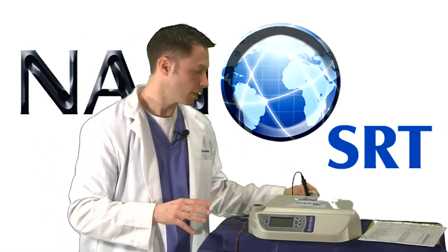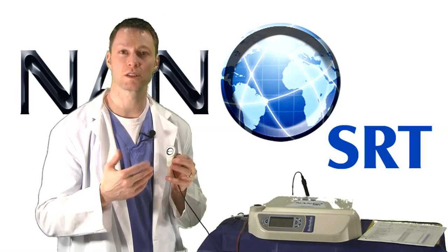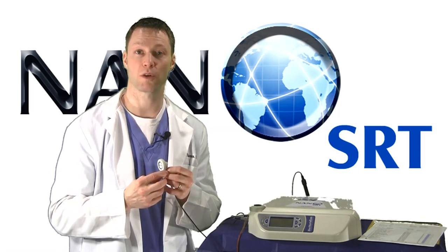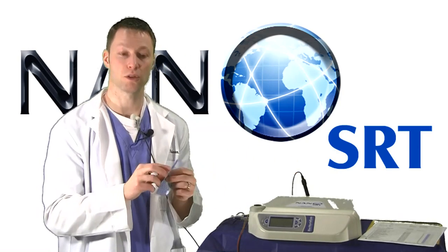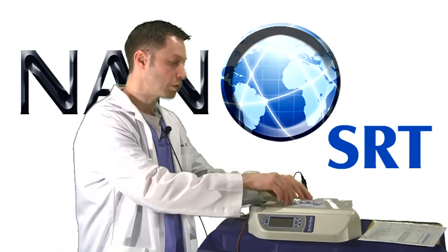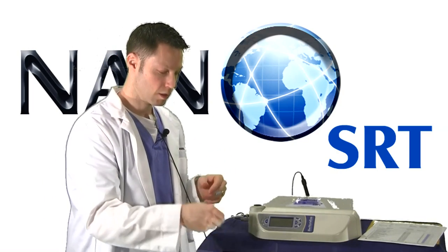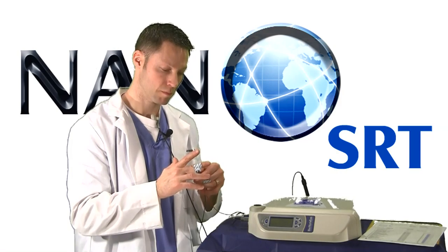Again, the step-by-step. When we do the testing, we take the external antenna, we call it the focus, and we clip that to usually your collar. What this is doing is sending out the digital signal that mimics the item that we want to test for. We put that on the shirt collar. Step two is we take the electrodes and we place them on the measuring points on your hands. Then we clip those to the machine with the testing clips. And now we're ready to test.